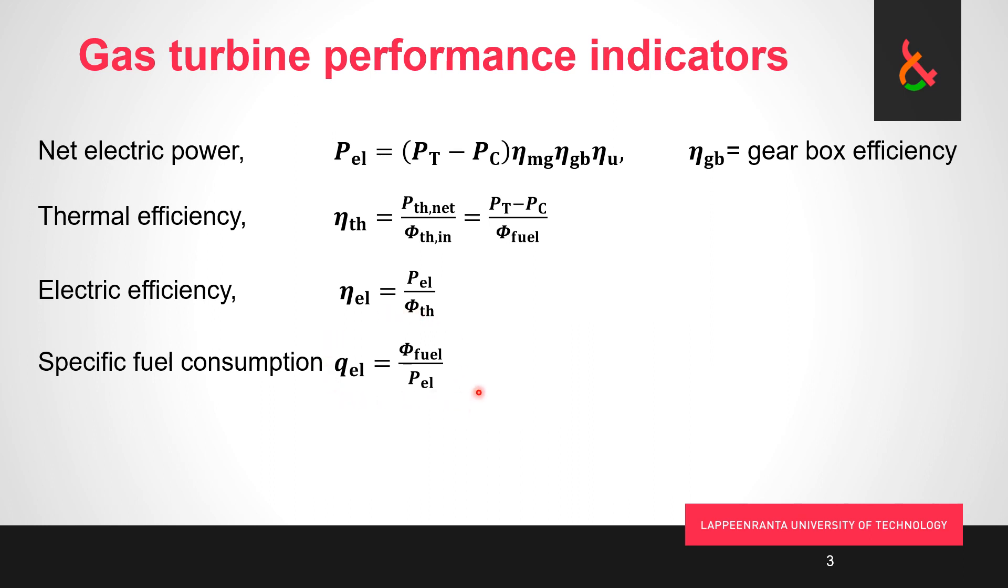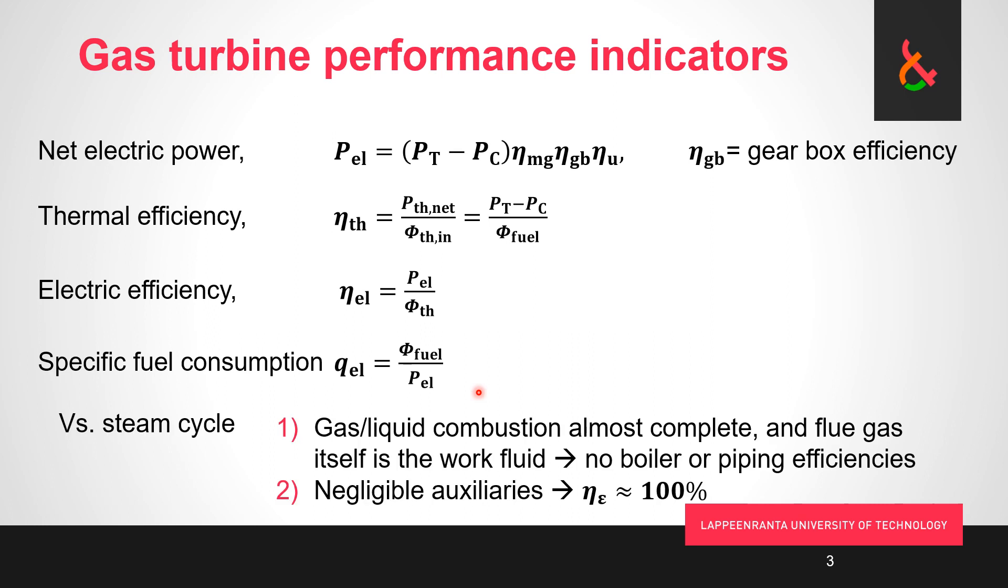And just as a summary, the major differences to the steam power plant process are that we get almost complete combustion of the fuel, and the flue gas itself is the work fluid. So no boiler and no piping efficiencies, negligible auxiliaries so basically auxiliary efficiency would be about 100%, and that's why our electrical efficiency is only very slightly less than our thermal efficiency. We get the electrical efficiency when we multiply this here with these three fairly high efficiencies.